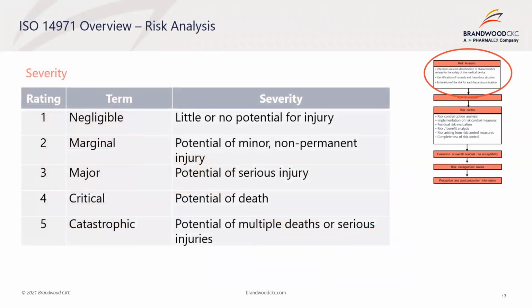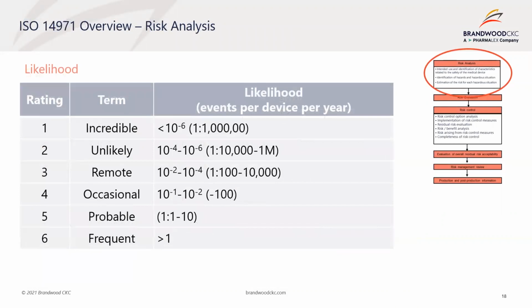The severity and likelihood of occurrence are based on criteria or rankings defined by the manufacturer. Here's an example of a severity matrix based on a 5-rating scale. The ratings range from negligible to catastrophic to define the severity of harm to the patient or user. Here's an example of a likelihood matrix based on a 6-rating scale. The ratings range from incredible to frequent, which defines the likelihood of an event occurring per device per year.